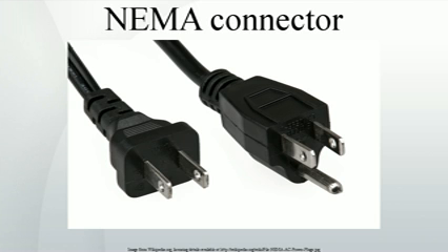The 14-30 has a rating of 30A and an L-shaped neutral blade. The 14-50 has a rating of 50A and a straight neutral blade sized so that it does not fit in the slot of a 14-30. NEMA 14-50 devices are frequently found in RV parks, since they are used for shore power connections of larger recreational vehicles. Also, it was formerly common to connect mobile homes to utility power via a 14-50 device. Newer applications include Tesla Motors' mobile connector for vehicle charging, which recommends the installation of a 14-50 receptacle for home use.